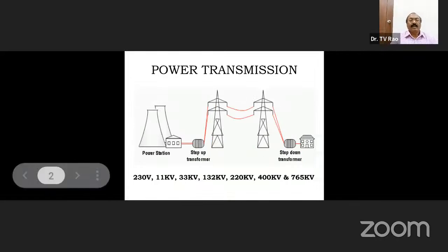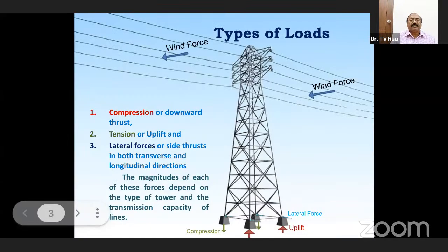We come across rivers also, so there we need special structures. The load coming onto the conductors from one tower to another has a span of 300 to 350 meters. When it crosses a river, the span between towers becomes 850 to 1000 meters, but on ground it is usually 300 to 350 meters.